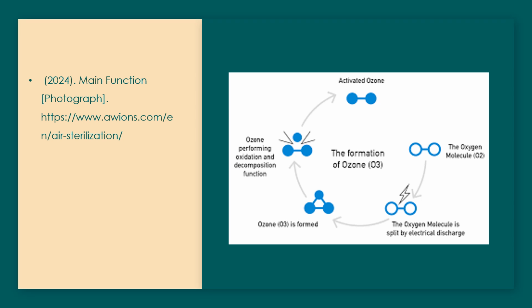Ozone sterilization. This is a gas that is known to be aggressive, oxidating, and an antimicrobial agent. This is produced inside the sterilizer by medical-grade oxygen. This is used on delicate medical instruments, usually such as endoscopes.